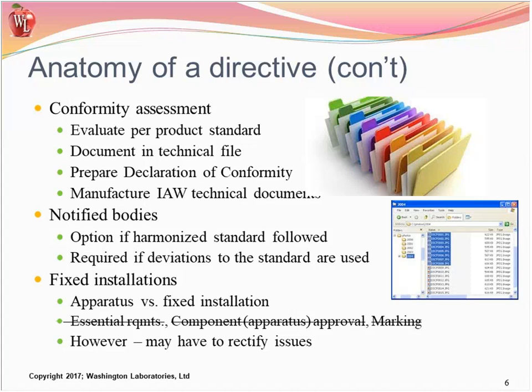I do want to discuss this fixed installation kind of process. The apparatus is a device that can be used and plugged in, installed, etc., and operates as its own entity. It may be incorporated into a larger device, and it may fit only into a larger device as in a fixed installation. For instance, if you have an apparatus that measures the speed of a conveyor belt, and that's the only thing it does, then outside of where the conveyor belt is located, this thing would not necessarily have an application. So the apparatus may fall under the fixed directive, even though it's being built separately, but it becomes evaluated under the fixed installation because that's the only option for using it.